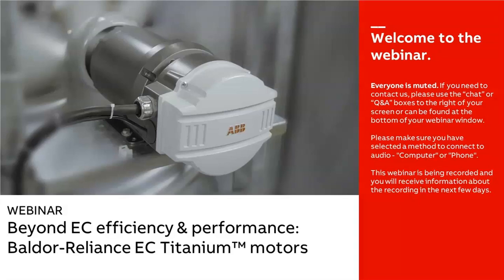Now, bear in mind, if you're running at lower voltage, the drive will power up and supply the motor, but it's going to draw more current. Less voltage means more current. So even though the drive has a wide voltage tolerance, we have to look at how much current it is going to be drawing if I'm only giving it 400 volts. Typically, the drives are oversized to the motor amps, so normally it's not an issue, but it's something to keep in mind. And it's just a straight calculation, 460 over 400 times the current.